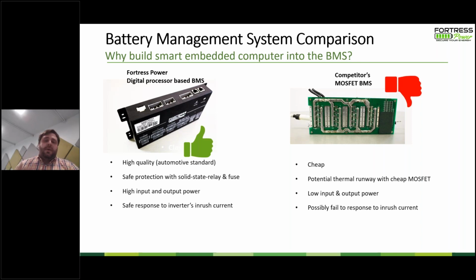You install a MOSFET-based battery management system, and then all of a sudden the battery charges at full capacity, or the equalization turns on and you thought you disabled it, but a firmware update on the inverter end reset the settings and turned equalization back on. Now all of a sudden your battery is charging at the full inverter capacity.